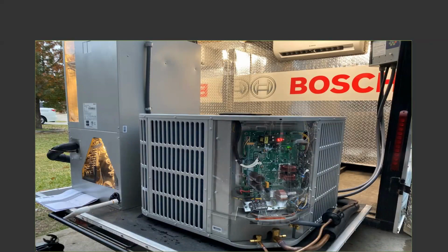Just want to show you a couple of things on this trailer that we're probably not going to talk about in depth, but it is over on the left-hand side, and it is the air handler. Brand new BVA multi-position air handler. If you need to put it to the downflow unit, you just take the cover off, take the coil out, flip the box, put the coil back in, put the cover back on. So there's no downflow kit for you to have.